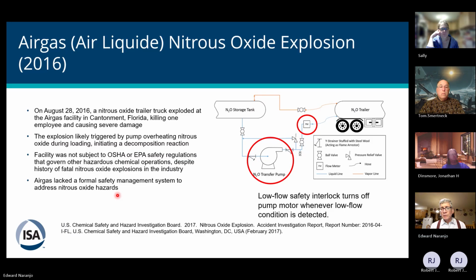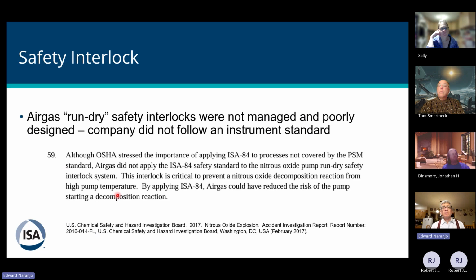So what went wrong, and what could be done to manage it? Well, the first thing is what is known as the safety interlock. Now, if we had a larger facility, much more sophisticated, a refinery, an LNG gas compressor station, there would be a full review of process safety for all of the processes. But right here, a safety interlock really didn't exist other than by the flow meter. And it is really not managed.